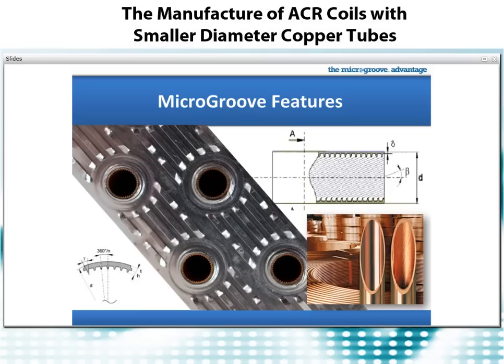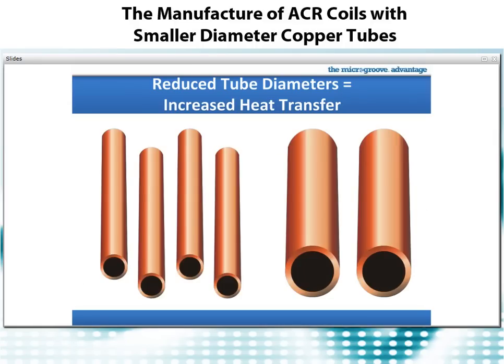When we combine the increased efficiency of internal enhancements with smaller tube diameters, one of the first things we notice is that it takes several smaller diameter tubes to equal the surface area of a larger diameter tube. But this is actually not a disadvantage — we have important benefits here. A big one is an increase in the surface area to volume ratio, equating to more heat transfer. With this increase in heat transfer, we don't need to match the volume of the larger tube to get the same amount of cooling. Using smaller diameter tubes, we can match the cooling of the larger tube with less volume, and that also means less refrigerant.